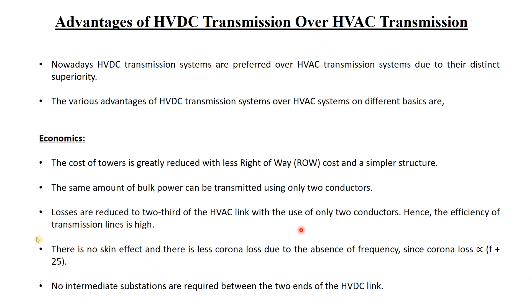HVDC is only used for transmission, not for distribution. When you are using HVDC for transmission, you are transmitting the voltage at a certain level, suppose 400 kV. You will not be stepping down the voltage anywhere. You start the voltage at 400 kV, after 200 km it will be 400 kV. If it needs to be stepped down, then we use a substation where the HVDC is converted into AC, then it is stepped down using a transformer. But throughout the 200 km span, when the DC is transmitted, a substation is not required, because reactive power compensation is also not required. So this investment in an intermediate substation is gone. That means there is a huge curtailment, or minimization, of investment. That is why HVDC is very much economical for long distance transmission.